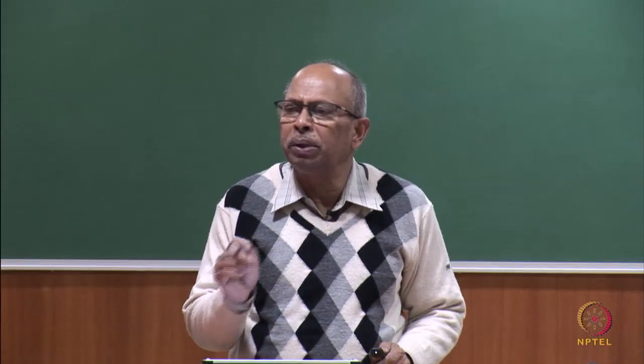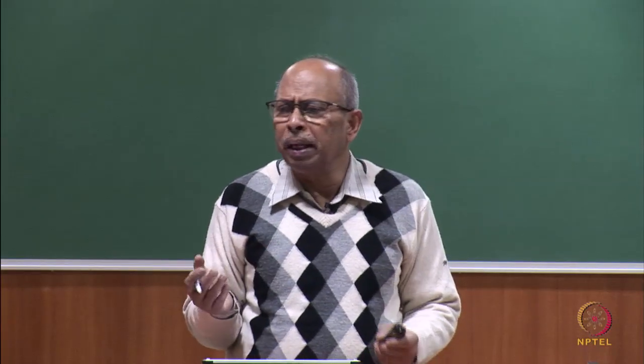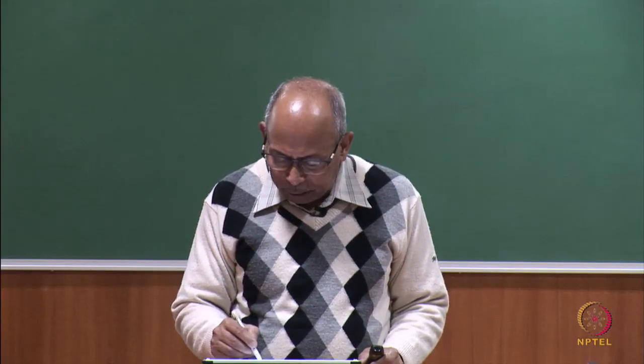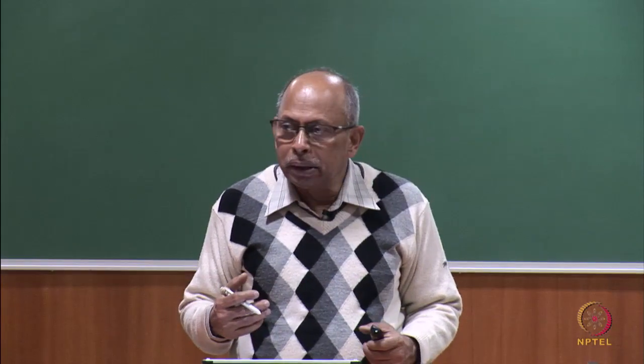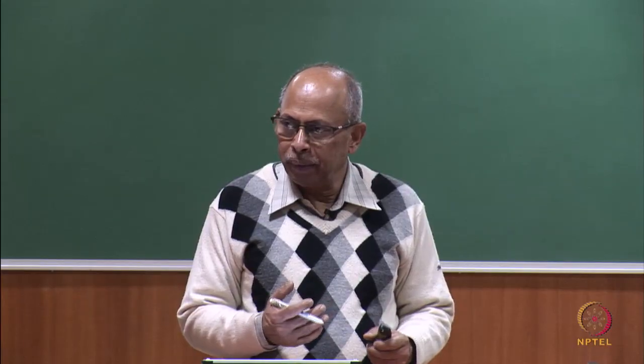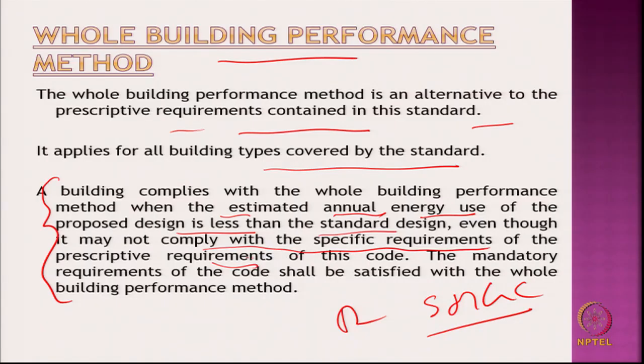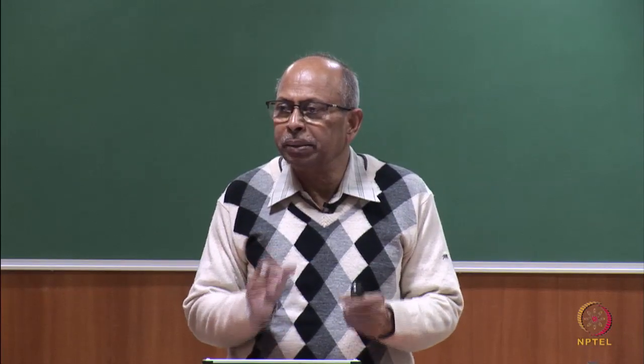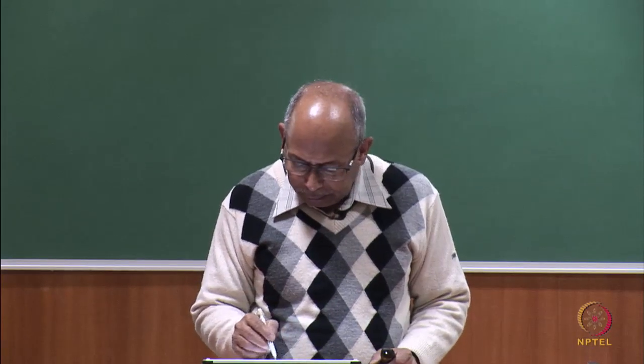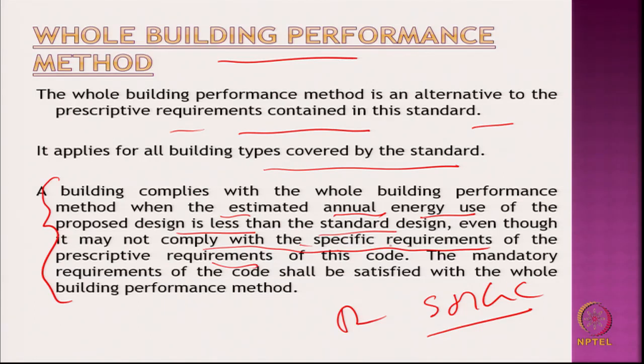Actually, the prescriptive one, if you remember, I said that it is generated based on life cycle costing and about 8-9 points regression. From that they actually found out what the insulation value should be, what the solar heat gain coefficient should be, and so on. Therefore, this is grossly conservative. So, if one looks at whole building performance, then it is much more flexible. You can do it in your own way and just show that this is better than the one that would follow the standard design. Okay.